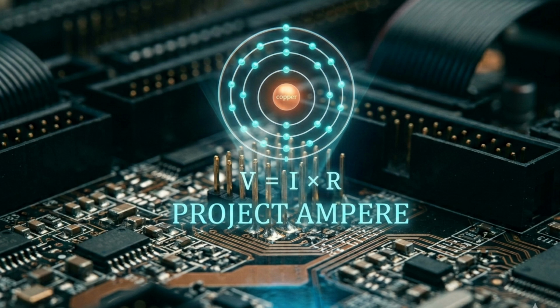So for a 5-amp lamp, I might actually need a switch rated for 40 or 50 amps. Roughly, yes. Or you verify that the switch manufacturer has already accounted for lamp loads and given it a specific lamp rating, but you never, ever trust the nominal resistive rating on the casing without knowing the load physics. And it isn't just lamps, right? Inductive loads are the other beast entirely.